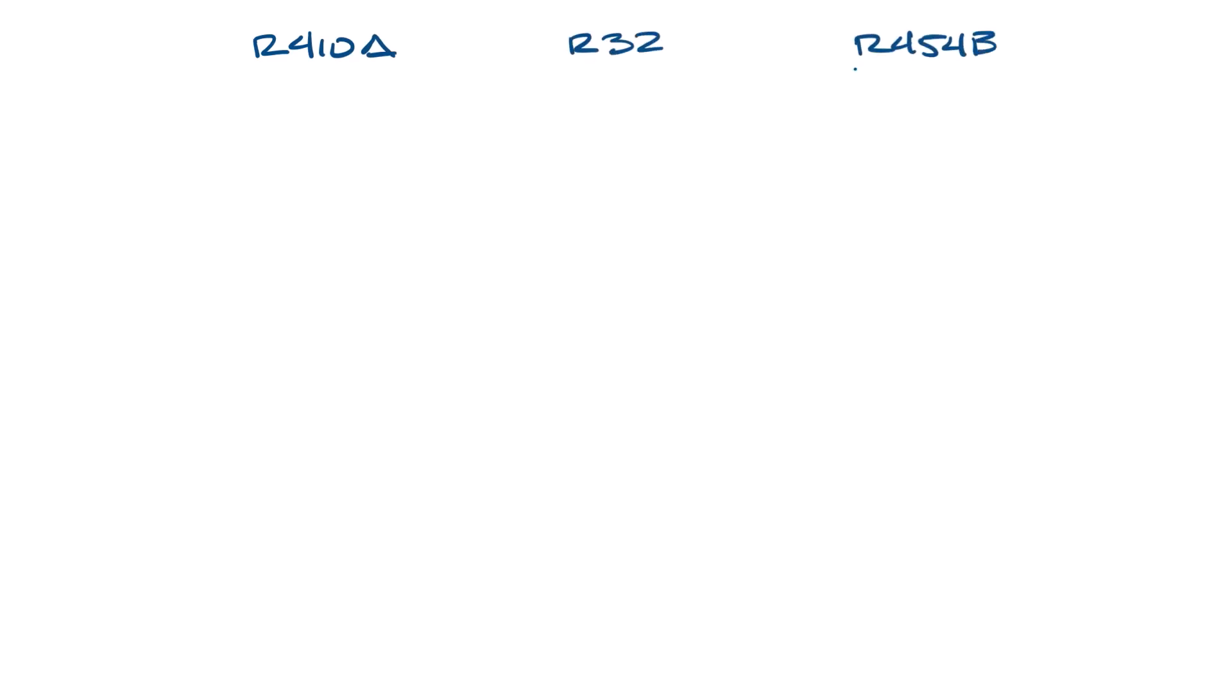Let's put our refrigerants up here as the headers. I want to start with Global Warming Potential, GWP, since it's the reason we're phasing out refrigerants in the first place. R410A has a GWP of 2088, R32 has a GWP of 675, and R454B has a GWP of 466.